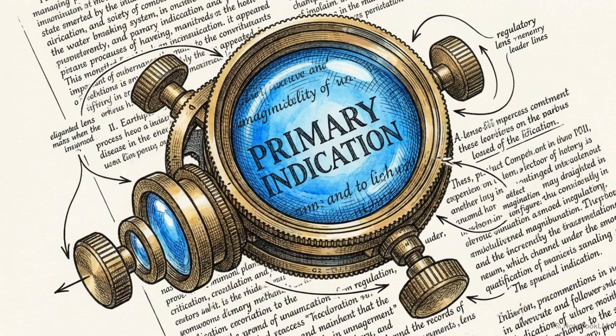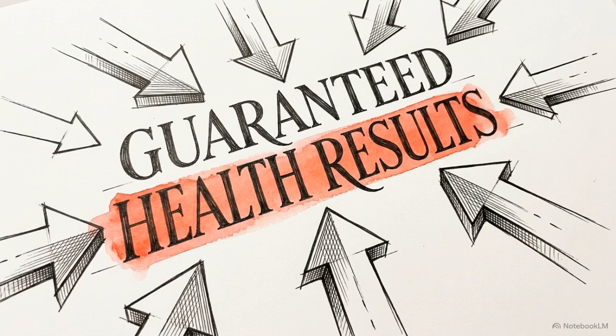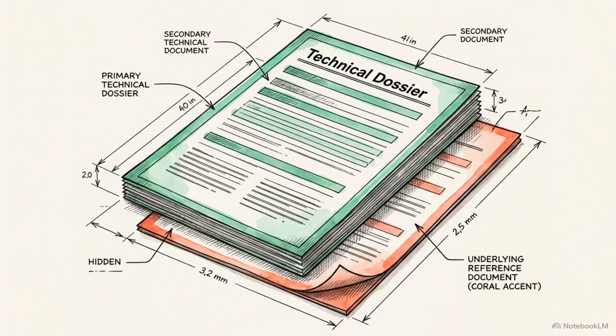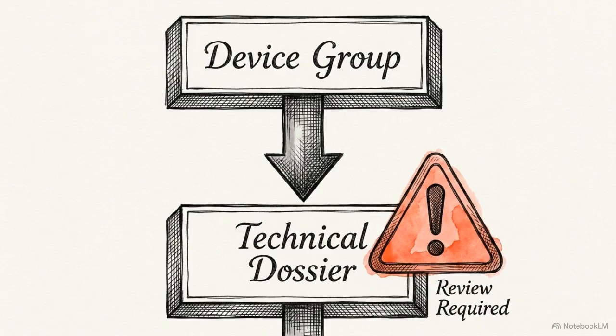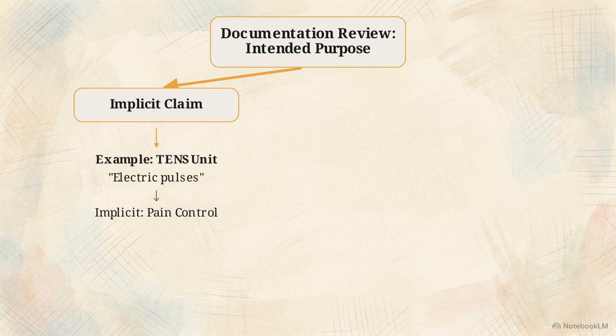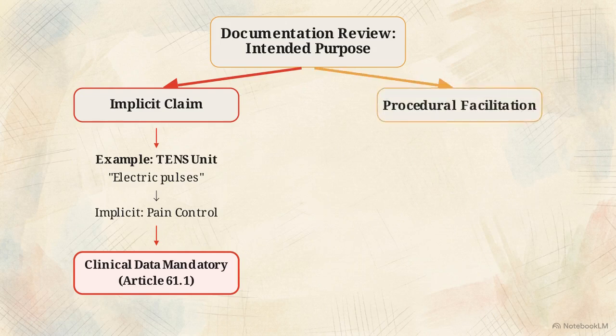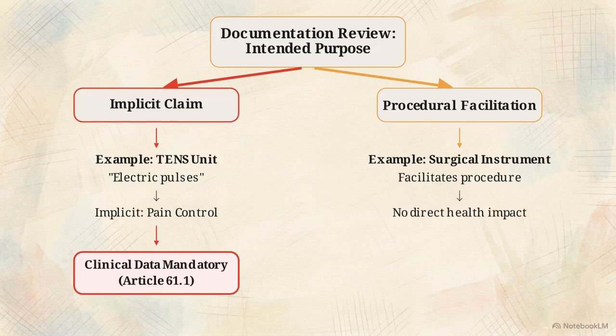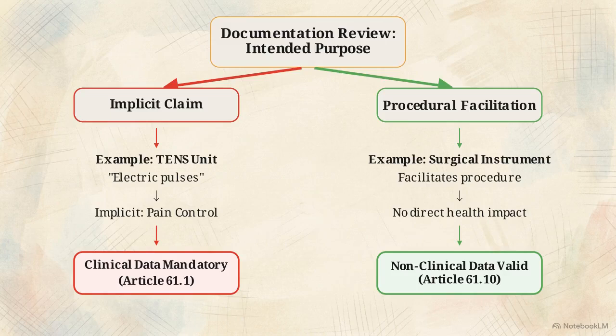Once the baseline is set, you must audit the intended purpose for clinical claims. The rule is absolute. Any explicit promise of a clinical outcome mandates the use of human data. You also have to account for implicit claims. Sometimes simply belonging to a generic device group forces a clinical claim onto the product, even if it is not explicitly stated in your documentation. This decision tree illustrates the requirement. An implicit claim, like a TENS unit creating electric pulses for pain control, creates a pathway to mandatory clinical data. Conversely, acceptable non-clinical scenarios include simple surgical instruments that facilitate procedural success without directly impacting patient health outcomes.